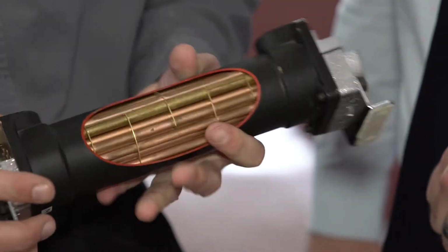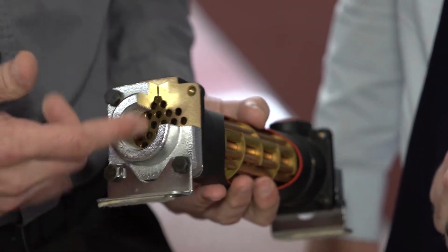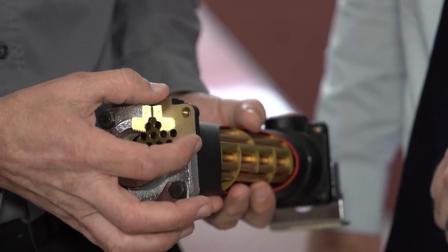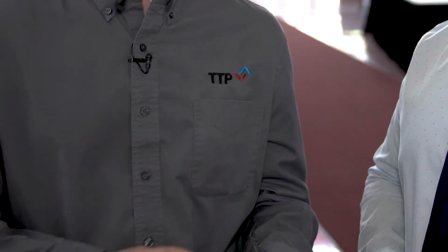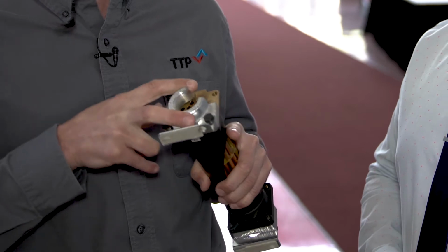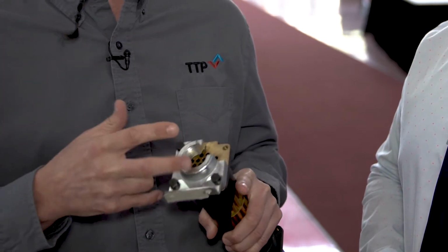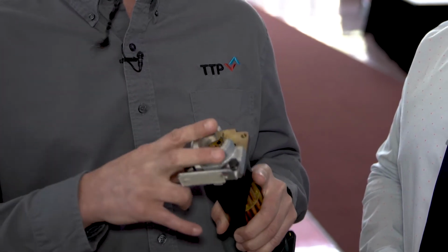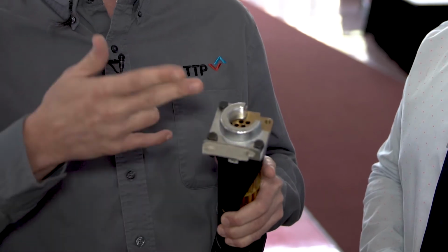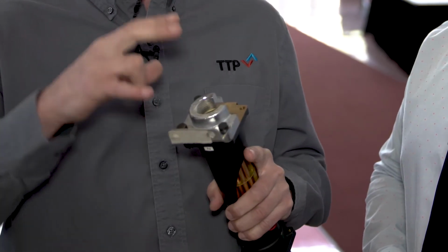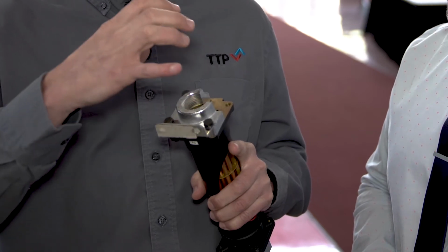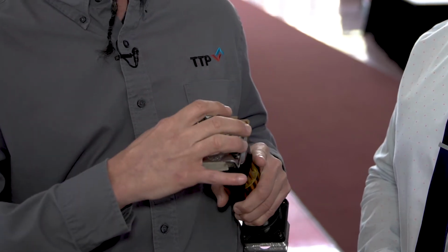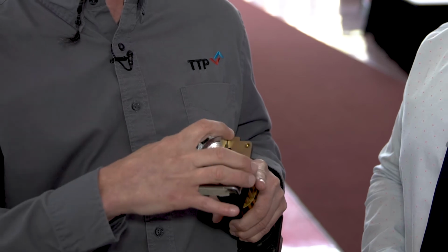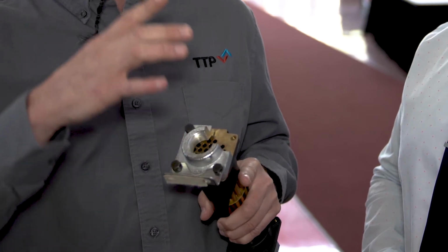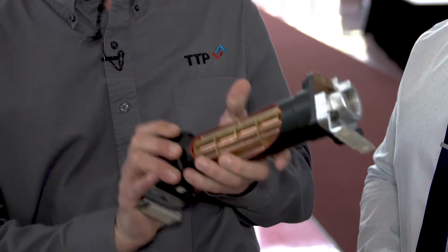So the way we're going to do this is on the water side of the heat exchanger, which is your two bonnets on the ends. If it goes in one side and out the other side, you have a one-pass heat exchanger. If you have two ports that are 6 hours apart from each other, at 12 and 6, you basically have a two-pass heat exchanger: your fluid goes in half the tubes and then comes back down out the other side. If you have two ports that are 3 hours apart from each other, so they will basically be in one hemisphere and two of the quadrants, you have a four-pass heat exchanger. It's important that you match that velocity profile.